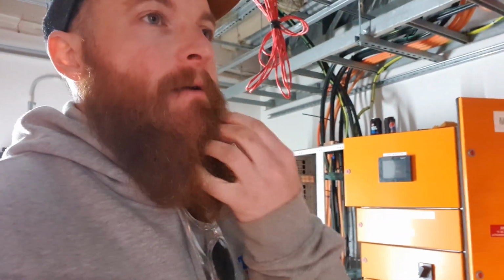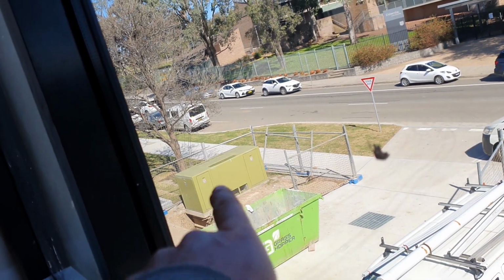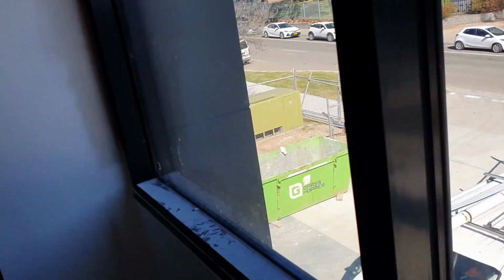Hey everyone, we've had a doozy of a day here. Substation down there, so that's where our cables go, coiled up in that pit there. Anyway, we had an extremely low insulation resistance rating between earth and one of the phases.